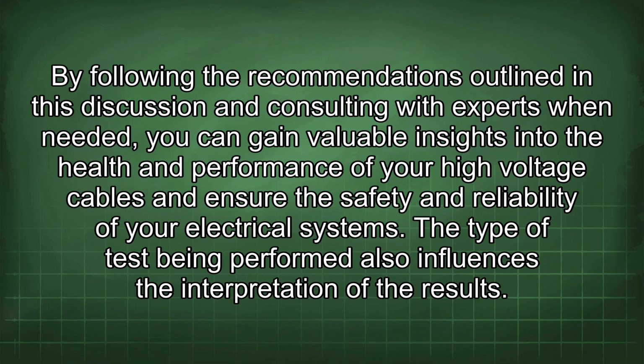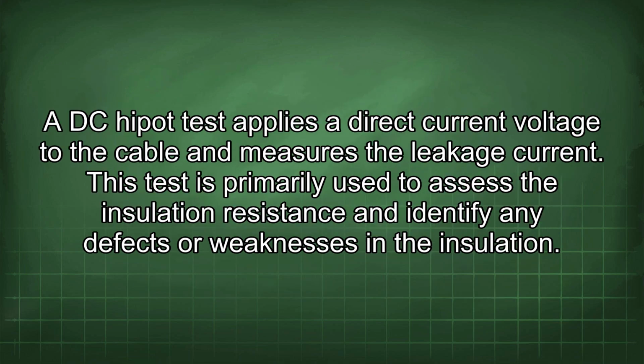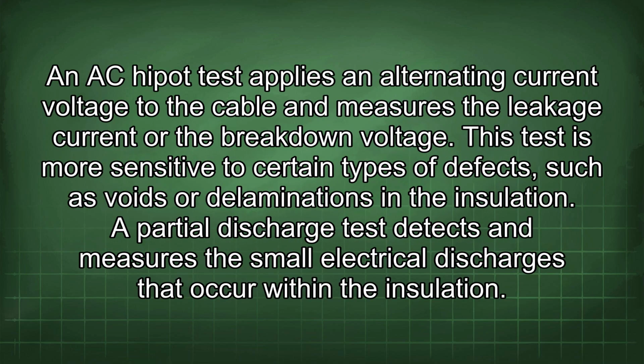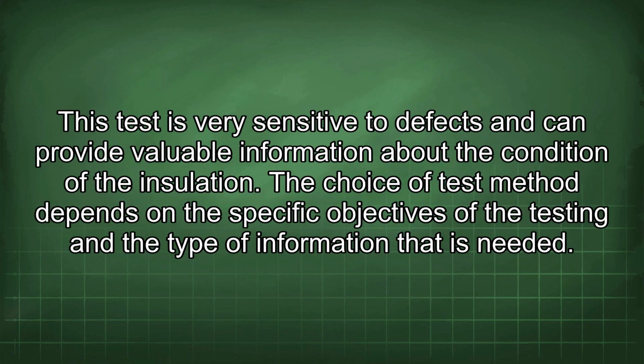The type of test being performed also influences the interpretation of the results. A DC hipot test applies a direct current voltage to the cable and measures the leakage current. This test is primarily used to assess the insulation resistance and identify any defects or weaknesses in the insulation. An AC hipot test applies an alternating current voltage to the cable and measures the leakage current or the breakdown voltage. This test is more sensitive to certain types of defects such as voids or delaminations in the insulation. A partial discharge test detects and measures the small electrical discharges that occur within the insulation. This test is very sensitive to defects and can provide valuable information about the condition of the insulation.